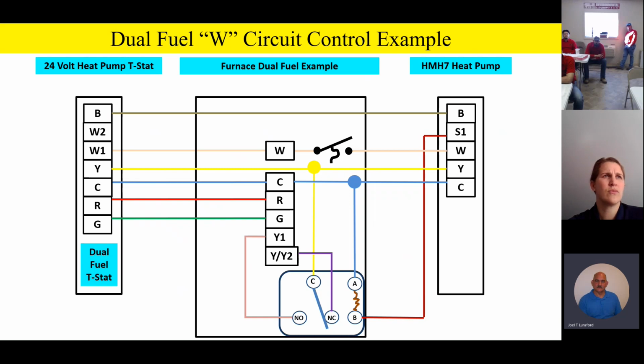That's how it's engineered. And so if you do dual fuel, to prevent short cycling of the furnace, throw one of those little construction thermostats in. You'll see how it's wired into the circuit right there. Everything wires exactly like it did before. It's just we're going to break that W signal from the outdoor unit to the indoor unit to give us the capability to help reduce short cycling of the furnace in the heating mode. So any questions or comments on that if you guys do dual fuel? Everybody good?